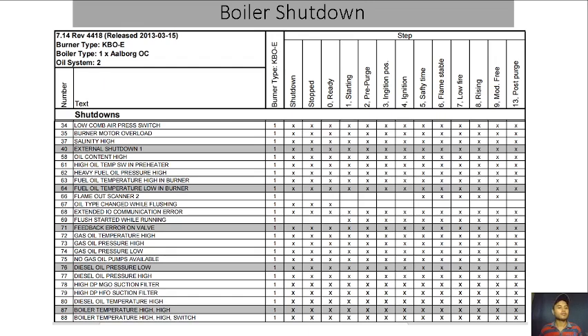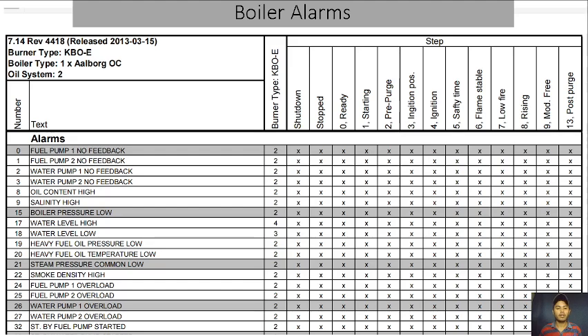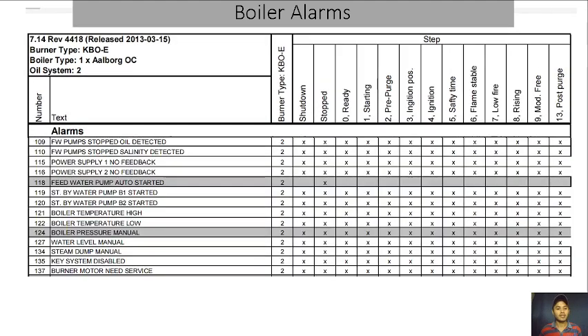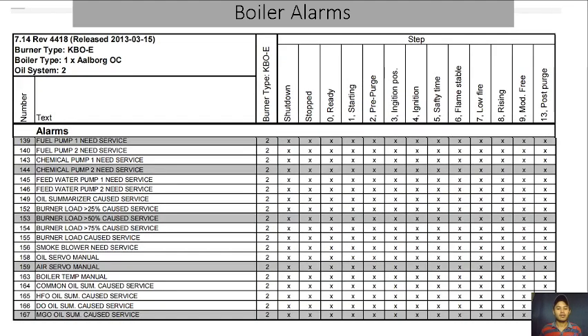Okay, so these are sample boiler shutdown and boiler alarms. There are more than 100 alarms that may be activated during our boiler operation. These alarms ensure that the personnel will be notified before damage occurs, or will be notified that there is a problem in the boiler. So that is the alarm.